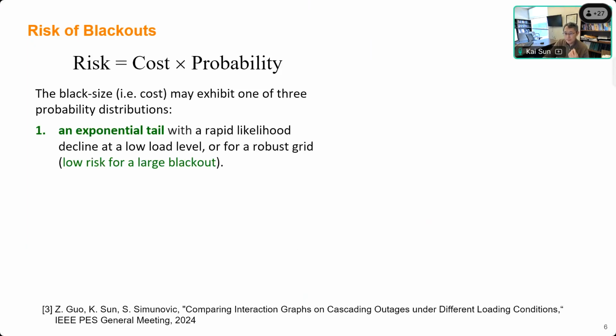There are three potential probability distributions depending on how strong your system is. If you're operating a very strong system—meaning each line has a large margin of security and reliability, or the load is very low, so each line has room to deliver more power—the probability distribution will likely have an exponential tail. This means low-cost blackout failures are much more probable than failures involving larger blackout sizes, so the risk for large blackouts is very low, and engineers need to focus on preventing the smaller size blackouts.